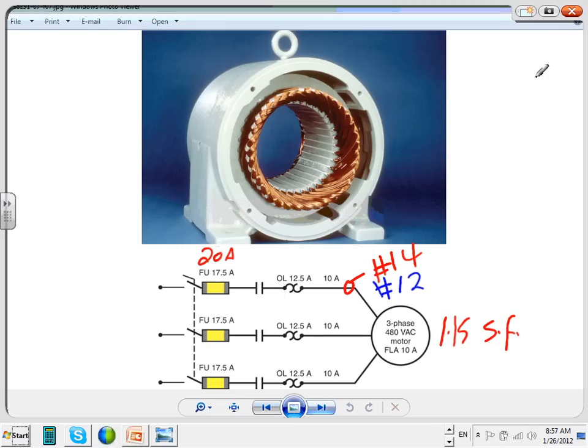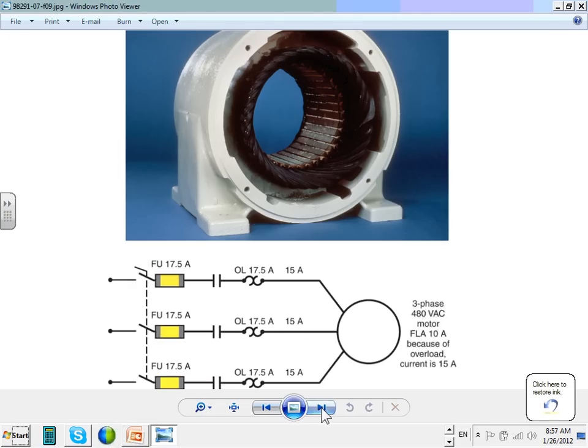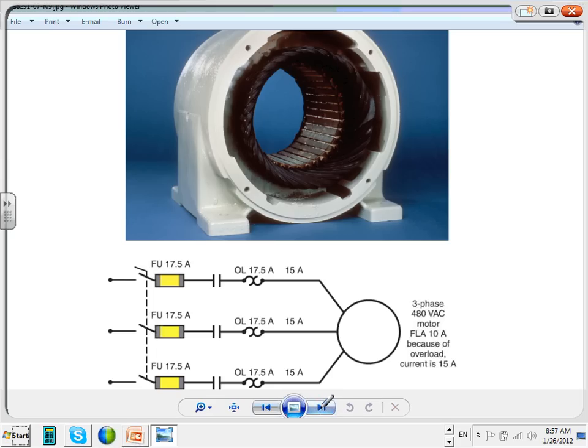If you overload that motor, look what happened. So what does overload mean? When they overloaded, did you guys see what happened to the motor for the top? What happened to the windings? Can you see what happened to the windings in the two pictures? You fried the windings. So you overload, the motor is rated for 10 amps and you're pulling 15 amps. How would you pull 15 amps out of a 10 amp motor? Add more load on the machine. The bearings on the machine are rusted and they're not working well, dragging the motor. Or the belt is not sized properly or is old and frayed and so forth. Because of the overload on the motor, look what happened.